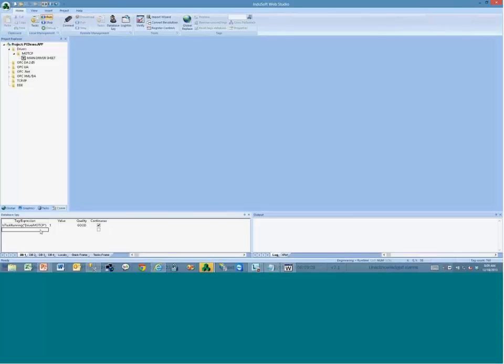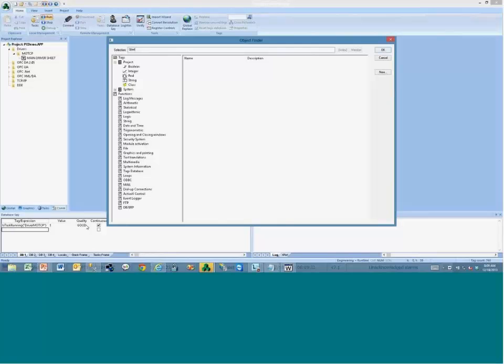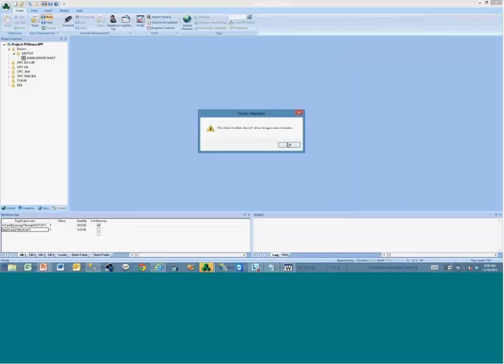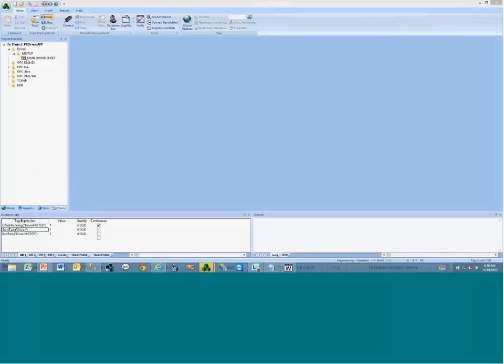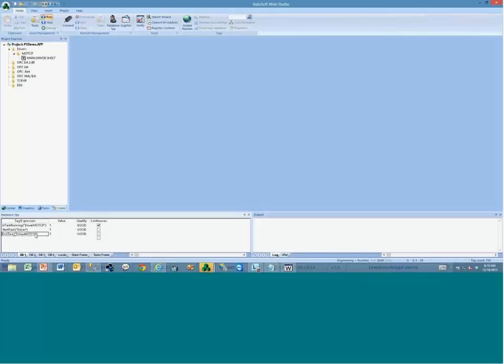By the way, I can even start the driver with those functions as well. So StartTask driver, which starts the driver, and EndTask driver Modbus TCP. As you see, when I run this function, StartTask driver toggles, it starts all the drivers configured in the project that are not running yet, and the function isTaskRunning driver Modbus TCP returns 1. And when I execute this function, EndTask toggle, it stops the driver.